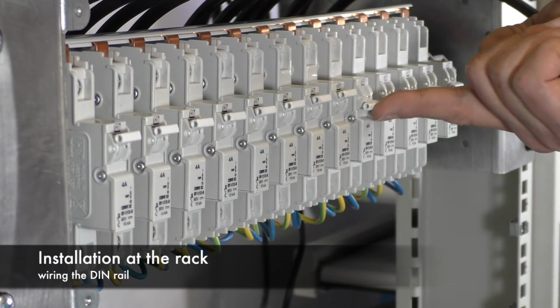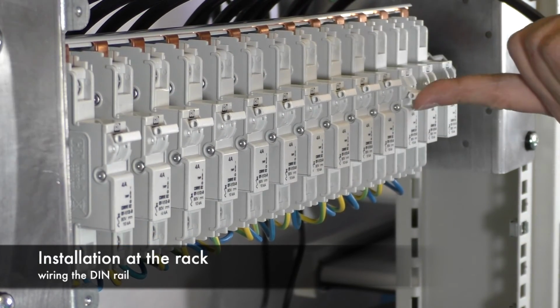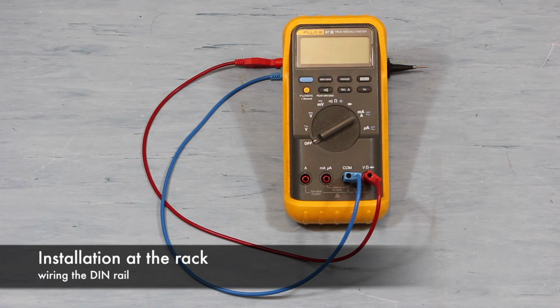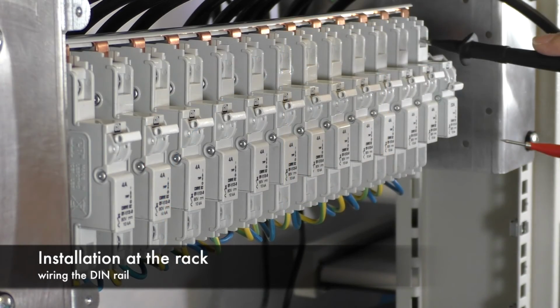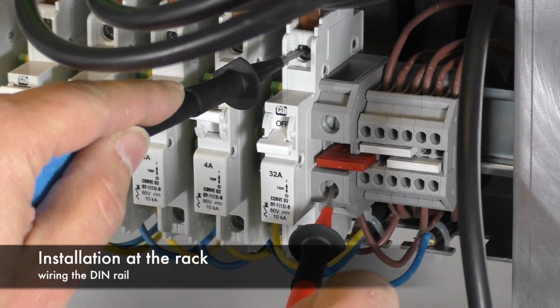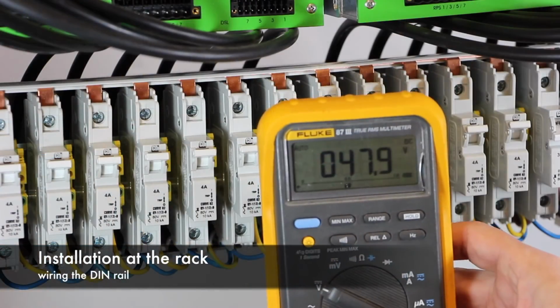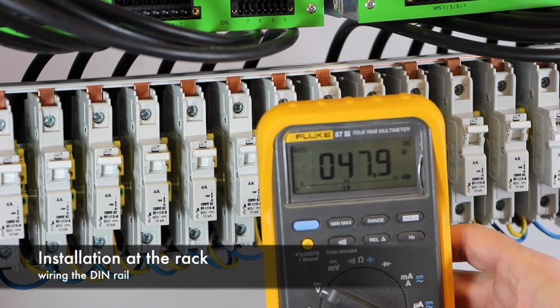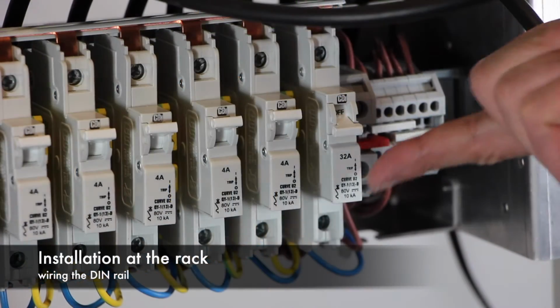Before you switch on the main 32 ampere circuit breaker, make sure that you have the correct voltage of 48 volts. Apply the multimeter at the negative pole of the main circuit breaker and the positive pole of the large feed-through terminal. If the voltage is correct, you can switch on the 32 ampere circuit breaker.